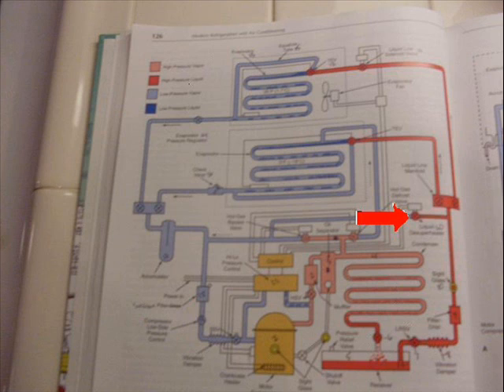So, sometimes things go bad, and the low side system gets too hot, the temperatures get too hot. So we have a computerized sensor that says, oh my gosh, the low side pressure is too hot. The compressor is not getting a cool enough vapor, and pop, the liquid desuperheater valve will open, sending a cooling fog of moisture droplets back toward the compressor. Now, I say a fog.